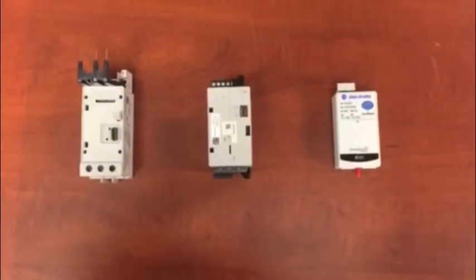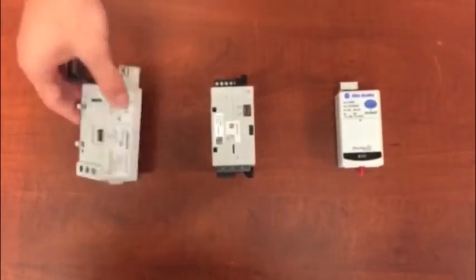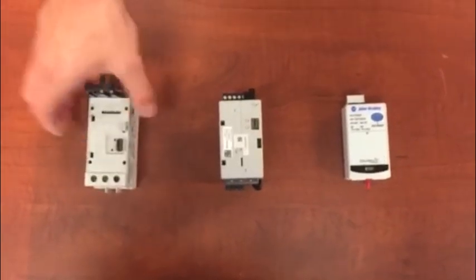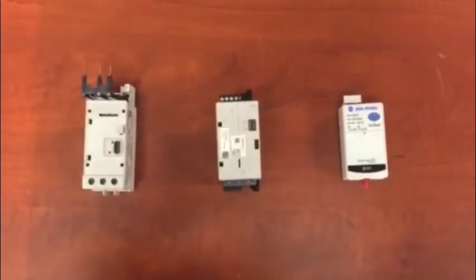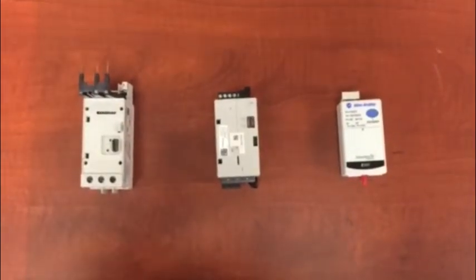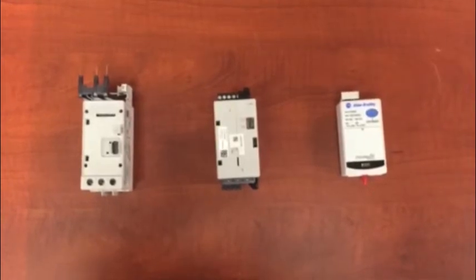The E300 is comprised of three modules. First, we have a sensing module. The sensing module can operate at amperages between 0.5 and 200 amps. It can sense current, ground fault, and voltage.